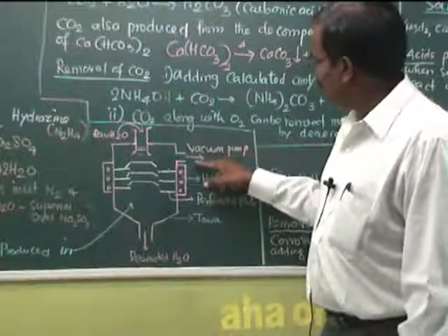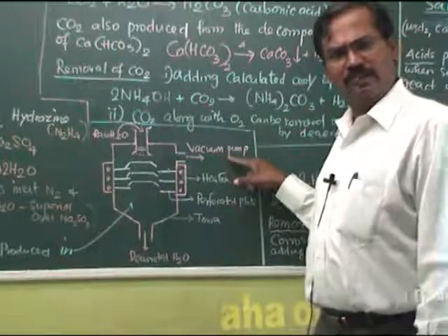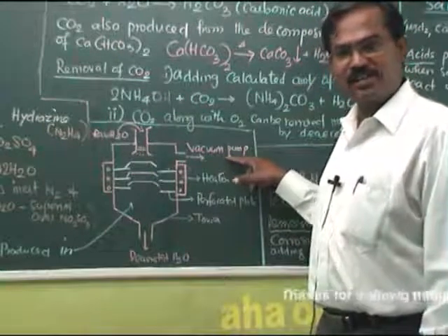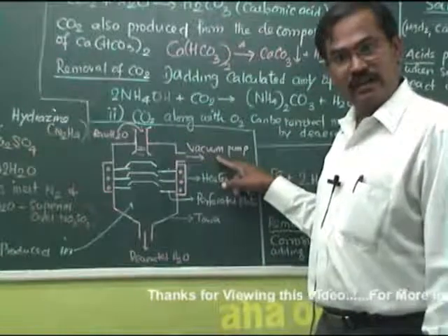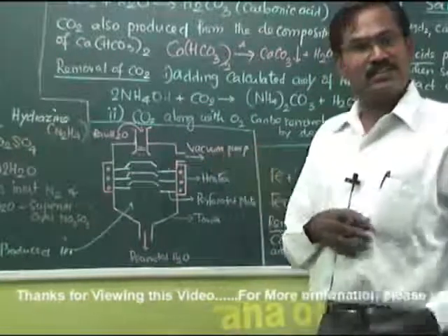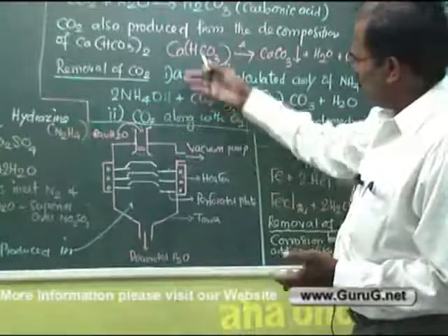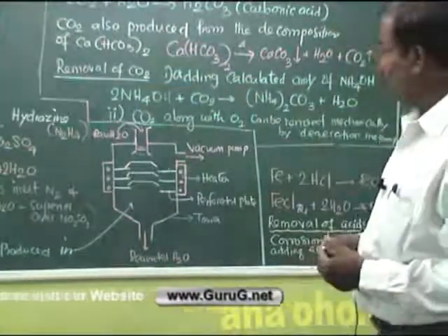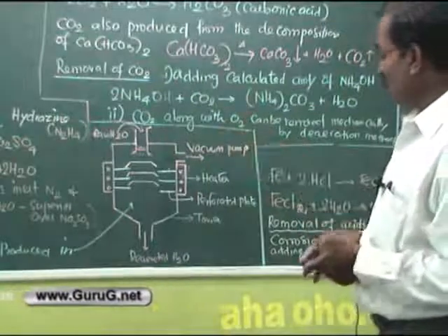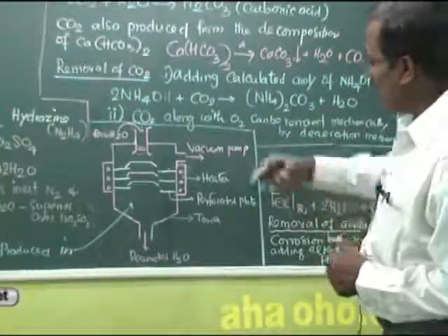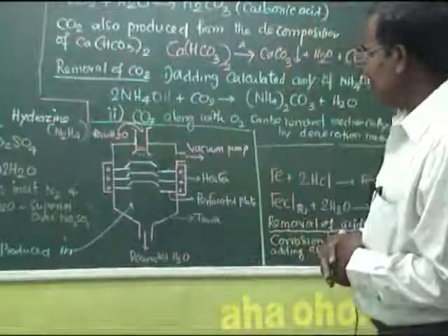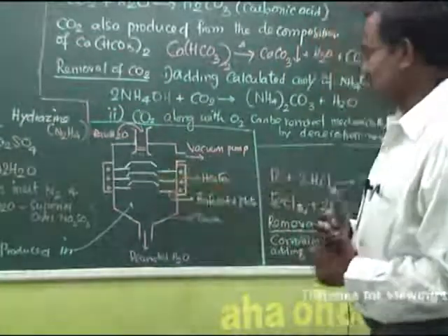And here this is attached to a vacuum pump. That means the pressure inside the tower is decreased; for that it is attached to the vacuum pump. So we are feeding the water which is having dissolved oxygen. From the top it is sprayed, and we have perforations as I specified earlier.